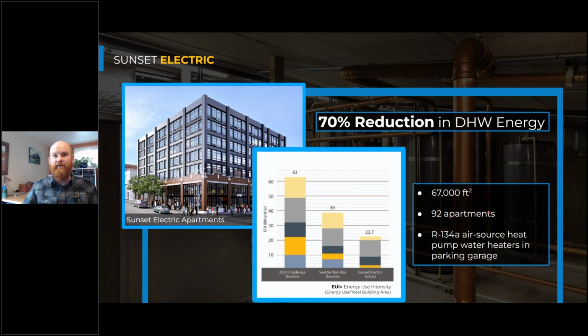It's a 67,000 square foot apartment building. There's 92 residential apartments, some 1-bed, some 2-bed, and a few studio apartments. And this building is using R134A Colmac air source heat pump water heaters in the parking garage. And those have been operating well. We've definitely learned a few lessons, as this was one of our early implementations of that Colmac R134A heat pump technology, but it has been operating at a relatively high coefficient of performance and really reducing the annual energy usage in this building. So we can see our 2030 baseline challenge.